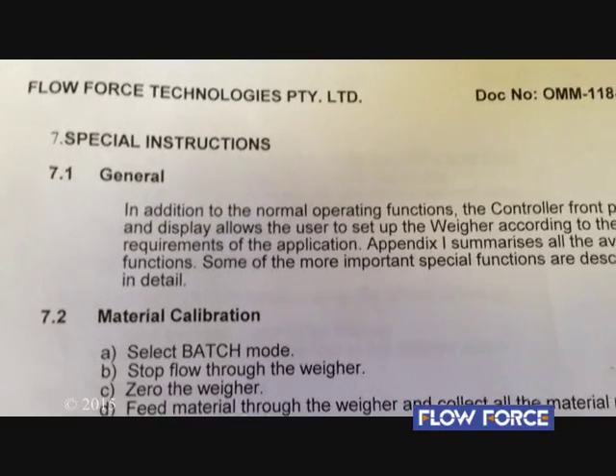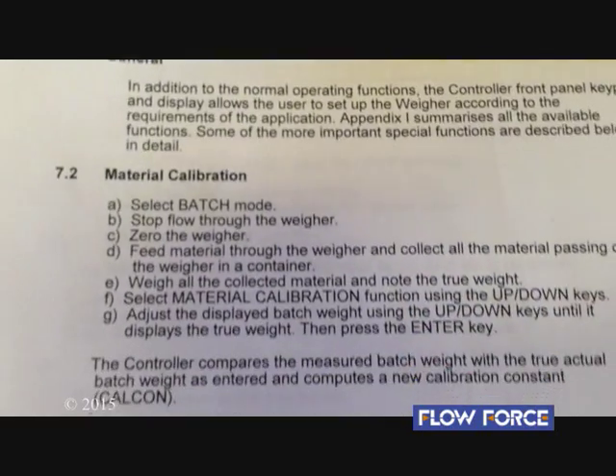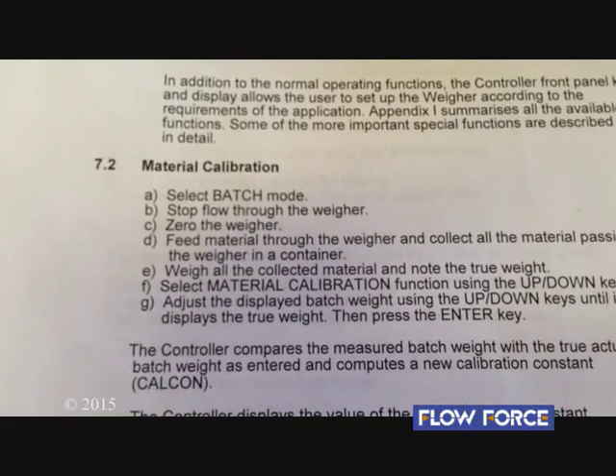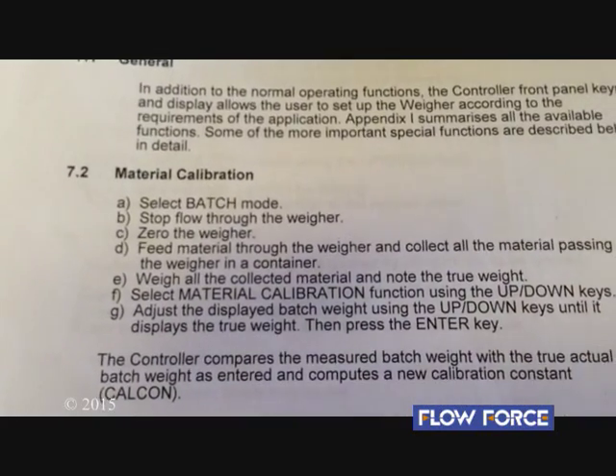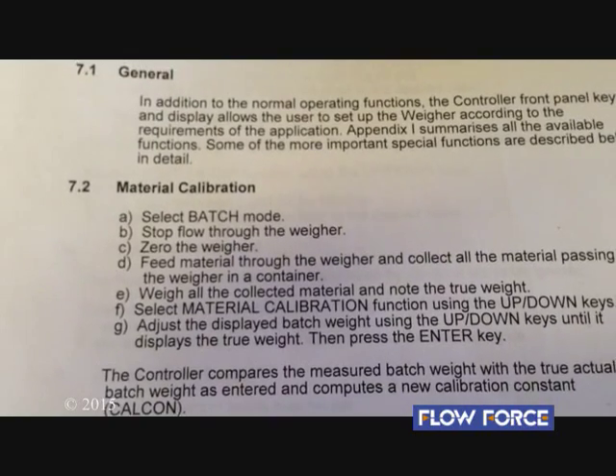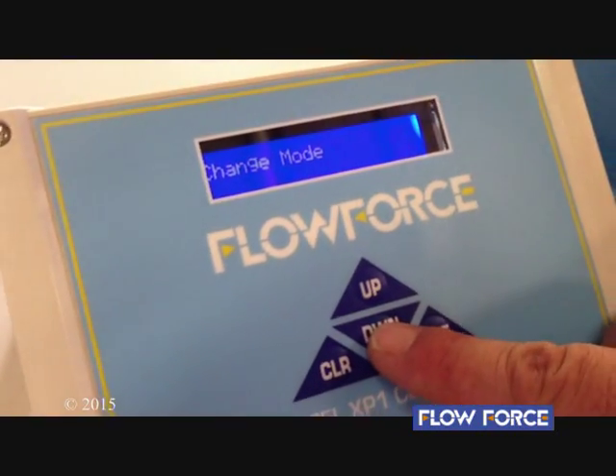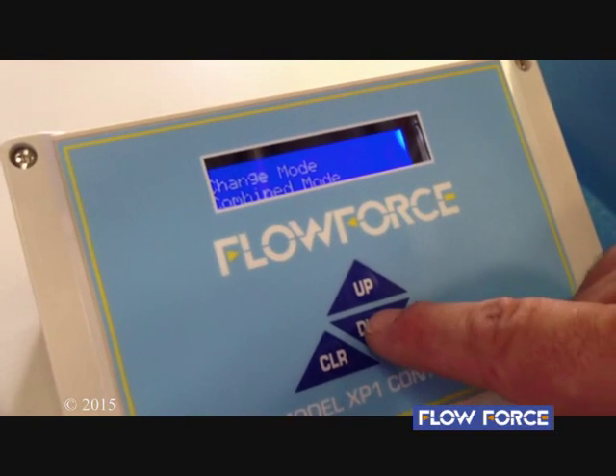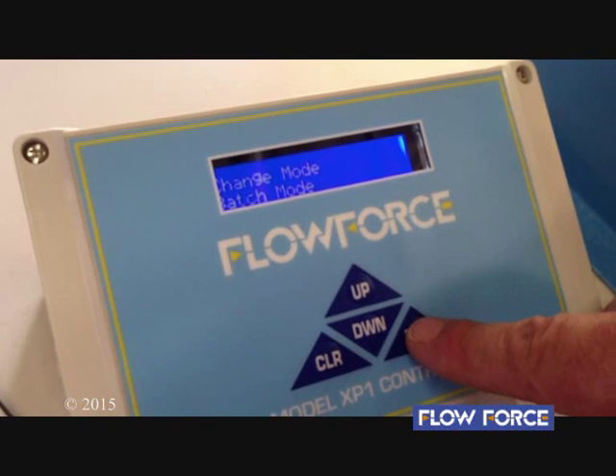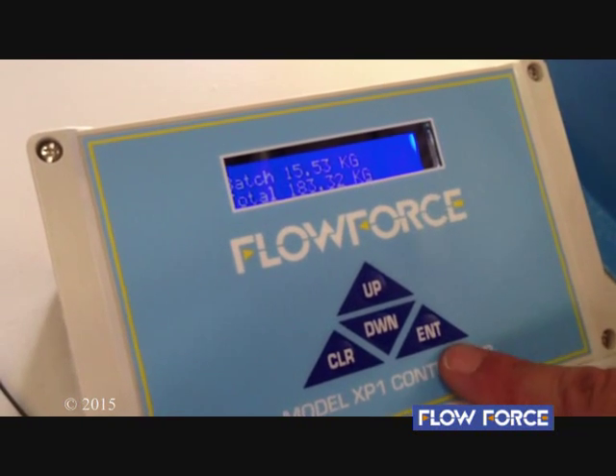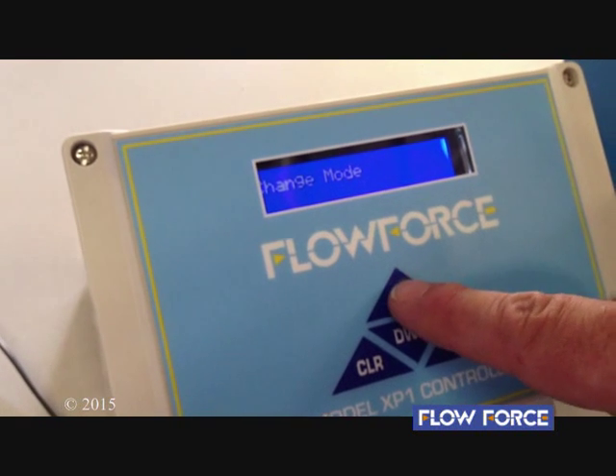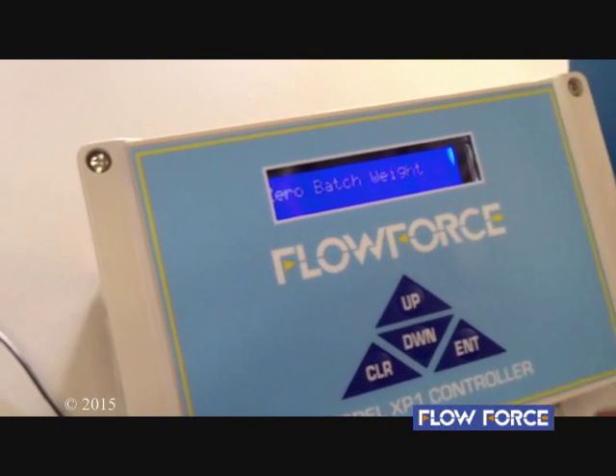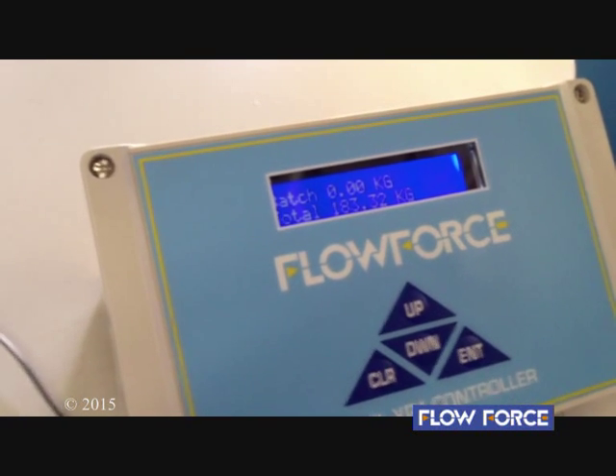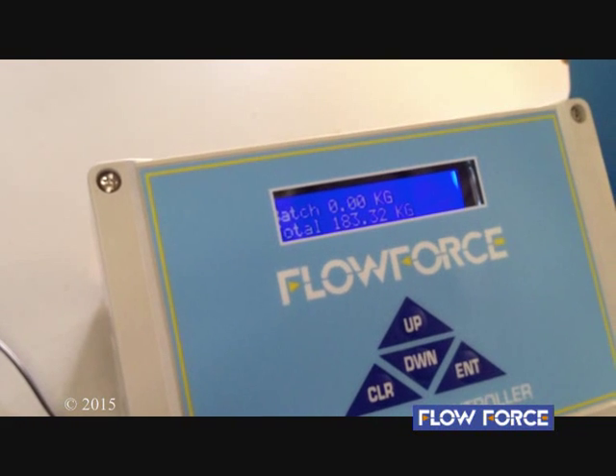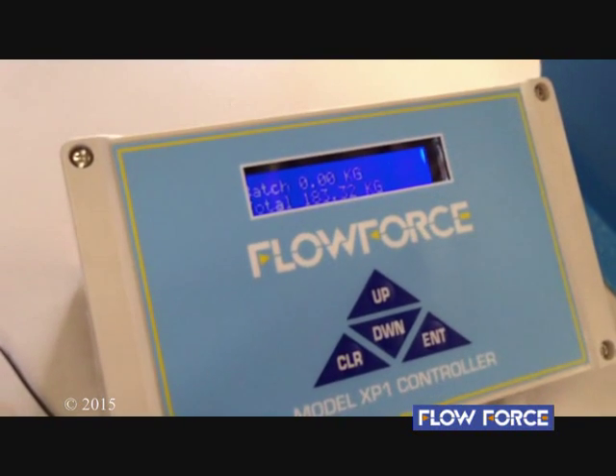Following the material calibration procedure in the flow force manual, section 7.2, we need to go to our XP1 controller, select batch mode, stop the flow through the weigher, and then zero the weigher. So we'll just show you how to do that on the XP1 controller. Using the up and down buttons, go to change mode, into batch, and now it's reading batch and total. We'll now stop the flow through the device and we'll zero the batch weight, and you'll see that comes back to 0.